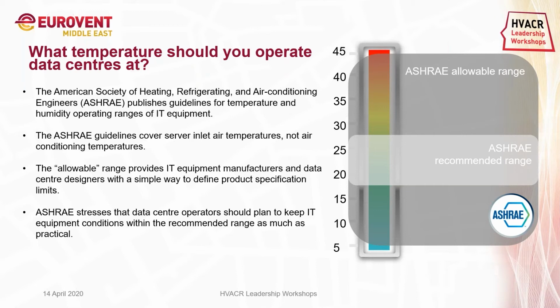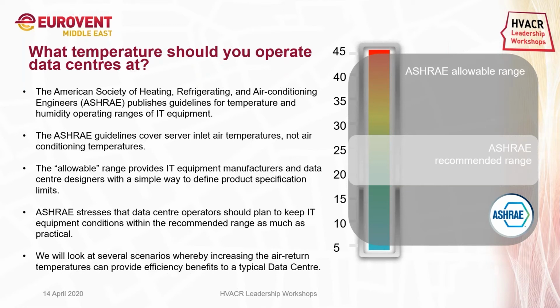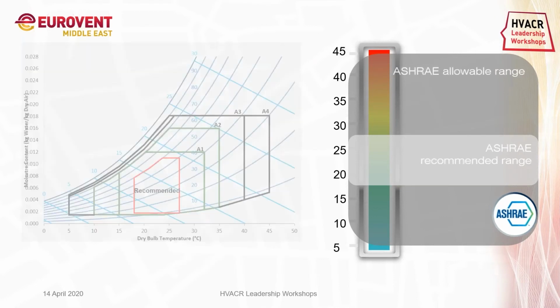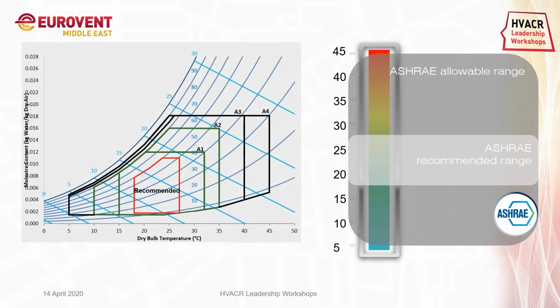So in the guideline ASHRAE releases, they are telling that the server inlet temperature should be in a range of 18 to 27 degrees Celsius. Now we will look at different scenarios whereby increasing the air temperature can provide efficiency benefits to a typical data center. This is what the ASHRAE recommended and allowable ranges look like when they are plotted on a psychrometric chart. You can see the recommended envelope; A1, A2, A3, A4 are the classification of IT equipment according to the temperature they can endure.